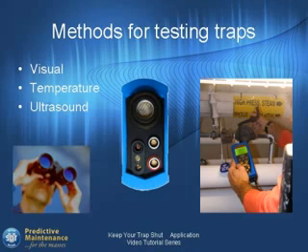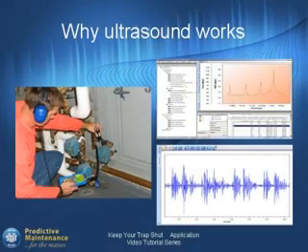Traps are tested online with live steam inside them. They are going to cycle at different stages, and those stages are dictated by processes in your plant. Choose the test methods that will give the best results and document your findings for trending. Ultrasonic data collectors like the SDT 270 sense high-frequency noise created by the turbulence of steam and condensate and the mechanical movements of the trap's inner components. Ambient plant noise is ignored while sounds inside the trap are translated to an audible level.